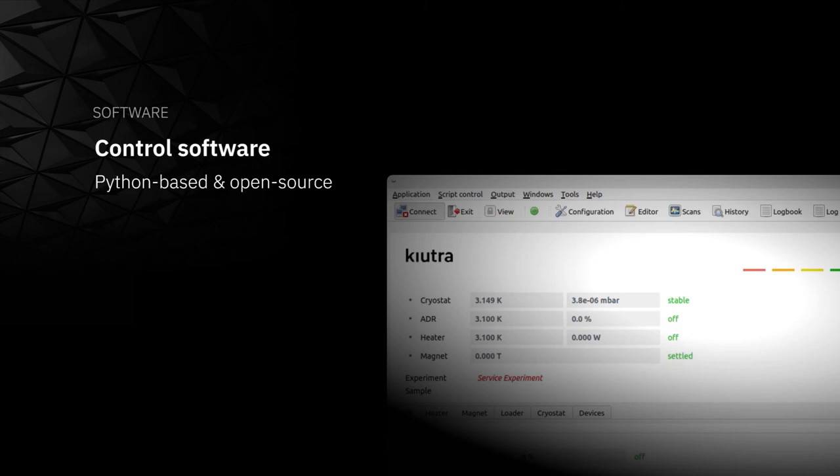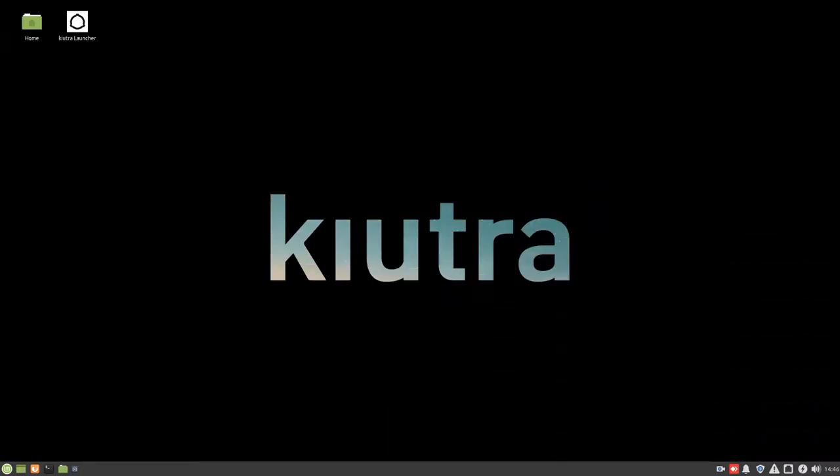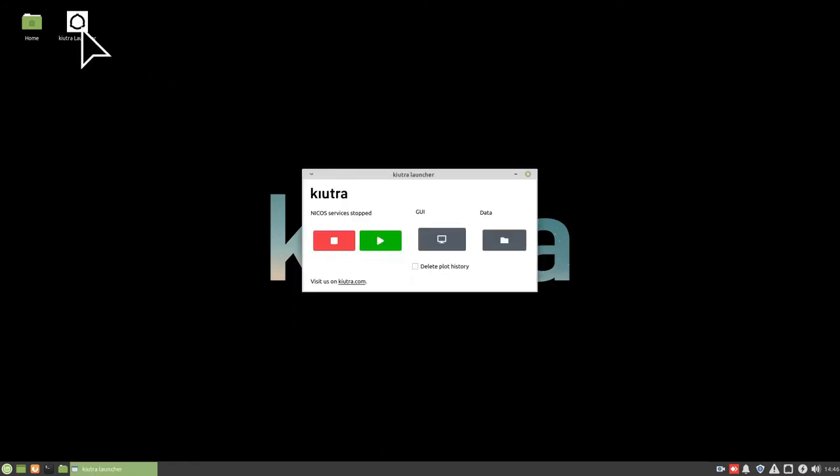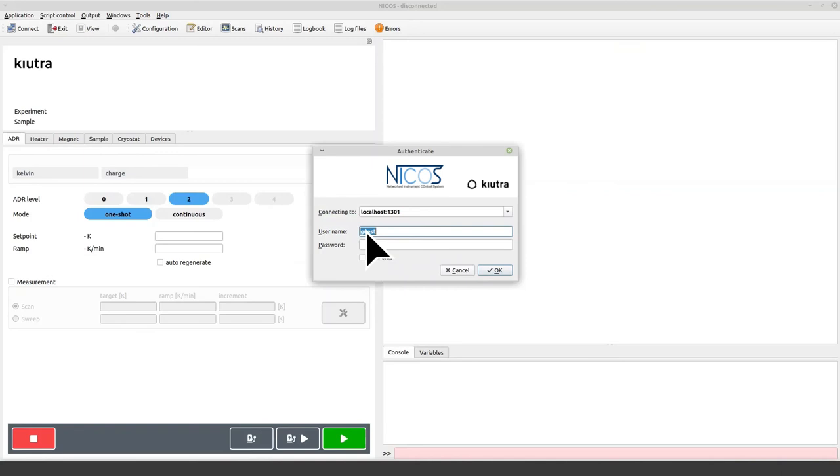I want to show you now how this kind of measurements can be done using our Python-based open source control software. We start the software by pressing the kiutra launcher symbol on the desktop of the supplied measurement PC. From the launcher we start the instrument control software by clicking the play button. Then we open the user interface by clicking the GUI button. You can now log into the graphical user interface by entering your username and password.